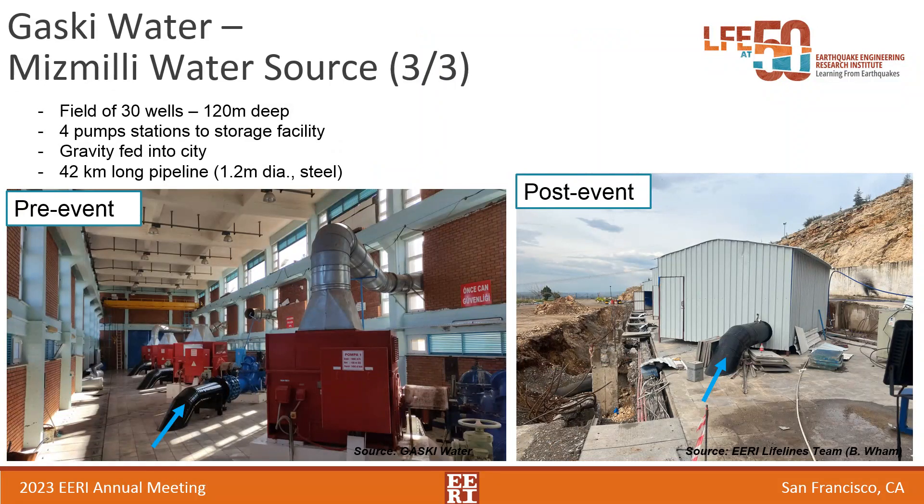That was two out of three of Gazi's prime water sources. The third is the Mizmilli water source — a field with 30 wells about 120m deep, with four different levels of pumping stations each containing four pumps. Pictures show the facility before the earthquake and at the time of our visit. The pumps continued to work despite the earthquake; they were down briefly, but once power was restored they resumed supplying water. However, the building itself was a safety concern and needed to come down. Engineers and laborers built steel structures around the pumps to protect them, deconstructed the surrounding concrete facility, and are working to rehouse the pumps appropriately.